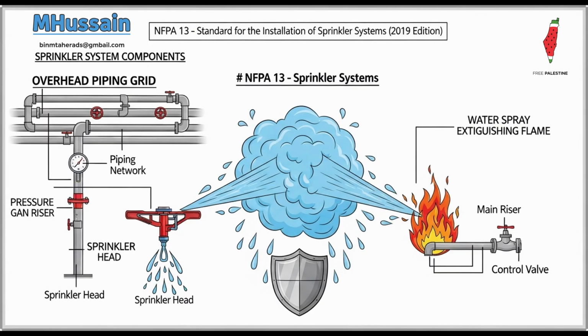Yeah, the takeaway here, I think, is that precision is absolutely paramount. And the highly prescriptive nature of NFPA 13 is really born from decades of fire testing, loss experience, and detailed risk analysis. The difference between an effective code compliance system and one that might fail under fire conditions, well, it can genuinely rest on whether that underground pipe is buried 11 inches or the required 12 inches below the bottom of a foundation footing, or whether that flue space in the rack storage is 5 inches wide instead of the required 6 inches. These detailed rules exist because those seemingly small variances can absolutely dictate whether a fire is controlled early or whether the entire system is ultimately overwhelmed. It truly is a masterwork of engineering codification that defines the rules of safety for so many buildings.